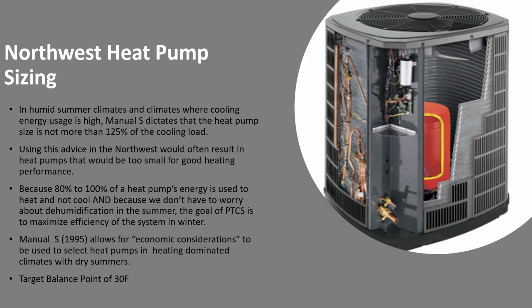So if we stuck to this 125% advice we get out of Manual S, we'd often end up with tiny heat pumps that use lots of electricity. In most parts of the Northwest, 80% to 100%, maybe less on the coast, of heat pump energy is used to heat and not cool. So we're much more concerned about the efficiency in heating than we are in cooling. If you really want to dig into Manual S, the 1995 version says that if you live in a heating-dominated climate with dry summers, which is most of the Northwest, you get to use economic considerations, and that's really what the balance point of 30 degrees does for us. Sort of gives us the best economics possible.